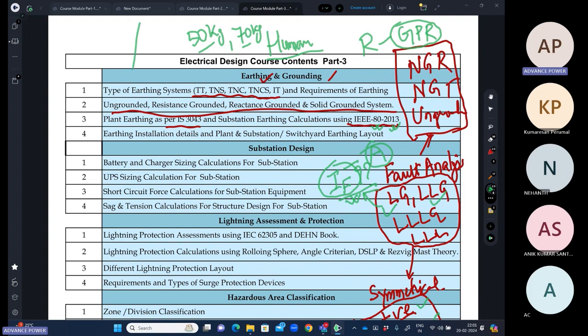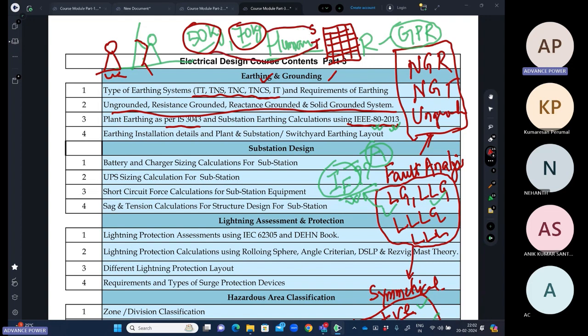It will show you that if a human is touching any metal body, earth fault current will flow in this way. When standing in a substation and not touching anything, if there is a fault, a voltage difference will develop between the two legs. We define these as touch potential and step potential. First we calculate the tolerable capacity of a human being, then we design the earth mesh of our substation, calculate the actual step and touch potential of this grid, and compare it with the human tolerable limit. Then we say my design is correct and acceptable.